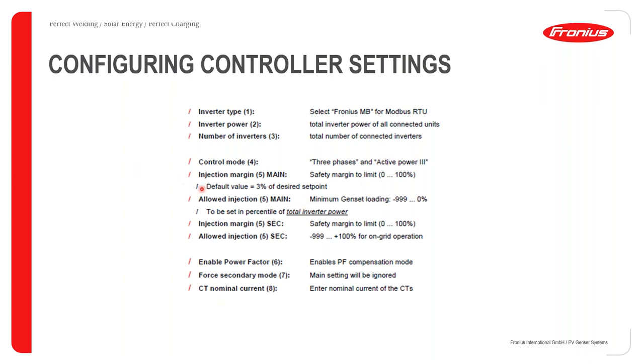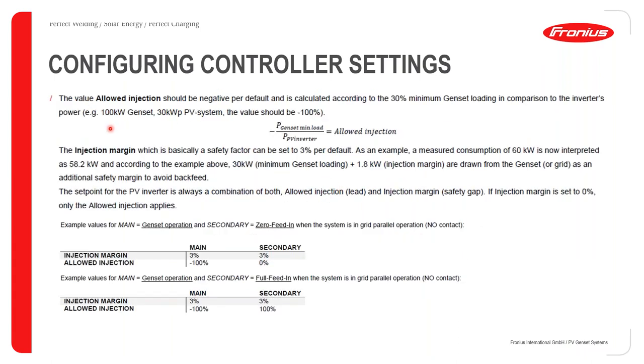Further down in the UI you will find injection margin and allowed injection settings. The injection margin is a safety margin — for example, setting it to 3% means 3% of the measured consumption value will always be drawn from the grid or genset, even with sufficient PV production. The allowed injection is based on the formula: negative of (minimum genset power divided by total PV inverter power), and this value differs system by system.